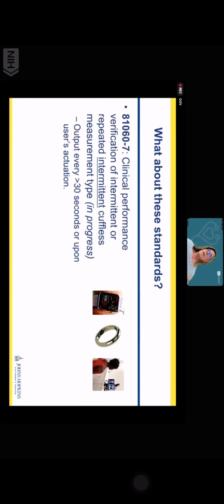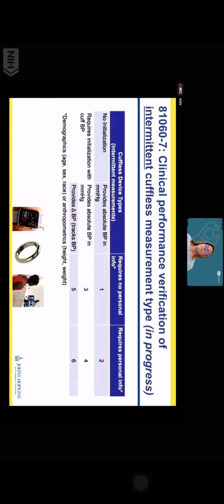Next slide. So what about how we test devices that give you intermittent cuffless blood pressure measurements? This is something, again, I said, that is in progress. These devices are different than the continuous ones because they give you an output less frequently, so more than every 30 seconds, or when the user actuates it, pushes a button to give you a measurement. Next slide. As we're developing the standard, we are developing it to address 6 potential and or existing devices on the market. Many of these devices, as was just described in the earlier presentation, require some sort of initialization and calibration. Many of them require personal information like demographics or anthropometrics.